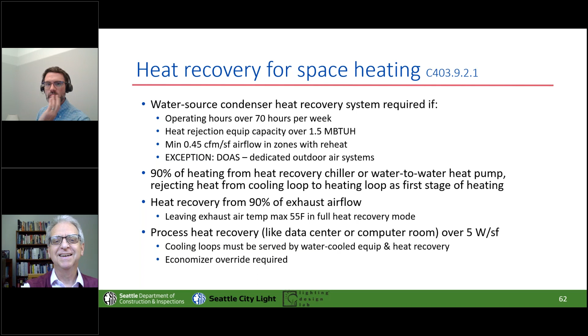Yes. So I want to drive home how weird most of the buildings are that fit in this section. Like for heat recovery for space heating, how many buildings are 70 hours per week, greater than 1500 MBH, with high enough loads for the 0.45 CFM per square foot to trigger cooling, and aren't already covered by a DOAS requirement? Hospitals, as well, was the only one I could come up with, maybe when they're big. The condenser heat recovery for refrigeration systems, that's clearly groceries, and it is something that new grocery stores are just going to do anyway, because you're putting heat in and then pulling it right back out through the open refrigerated cases. They want that heat recovery, or it just kills them in the pocketbook. So most of these are things where you think, well, that makes a lot of sense. But like Duane said, if you miss them in that special occupancy, that special case, it's really cruddy to find out at your permit set.